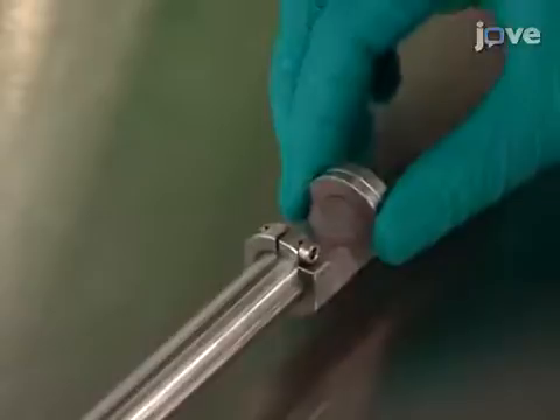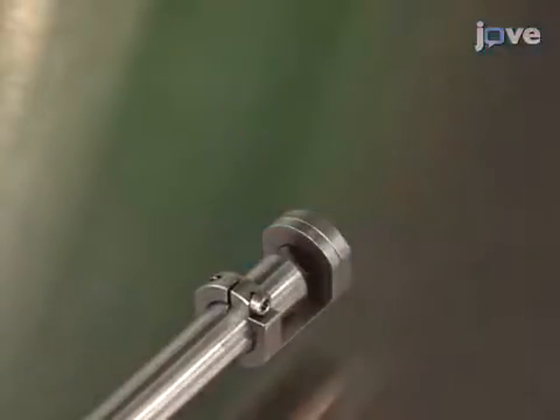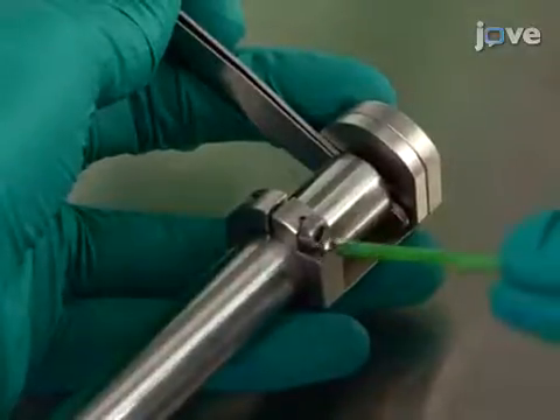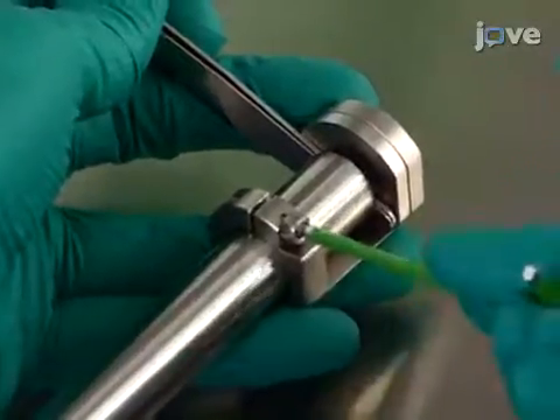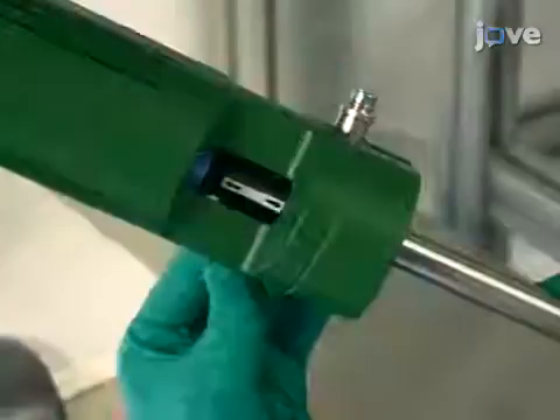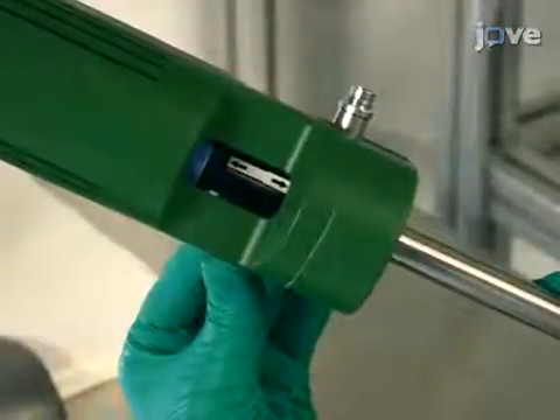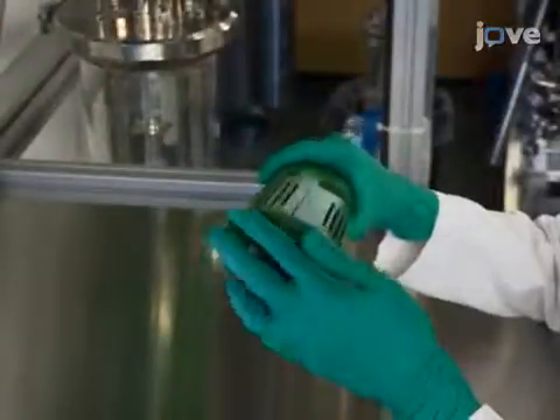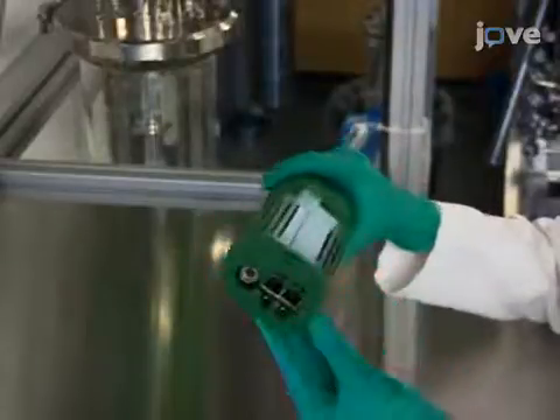Next, mount a reflection plane, such as a rhodium mirror, to the probe tip. Adjust the distance between the mirror and lens to 150 microns. Then adjust the screw at 100 microns to focus the objective. Generally, a high-speed CCD camera should already be connected to the endoscope probe, SOPAT VF.